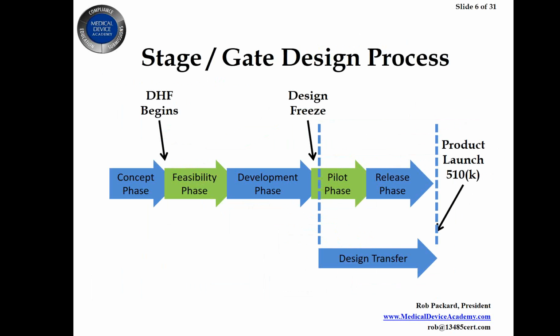But as long as you have one final design review, that's really the end of the design process that goes in your DHF. And it doesn't have to be linked to a 510K, but it often is, because the organization that's looking at your DHF and is most critical for most companies is the US FDA.